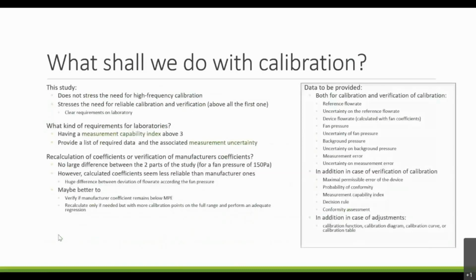So what shall we do with calibration? That was the main point of this study. This study does not really stress the need for high-frequency calibrations, because it doesn't seem that it deviates a lot after years. There is no big difference, but it stressed the need for a reliable calibration and verification, and above all the first one. So it's better to have less calibration but reliable ones than calibration every year, for example, but made by a laboratory with a high uncertainty.